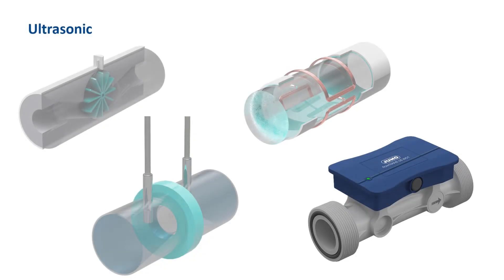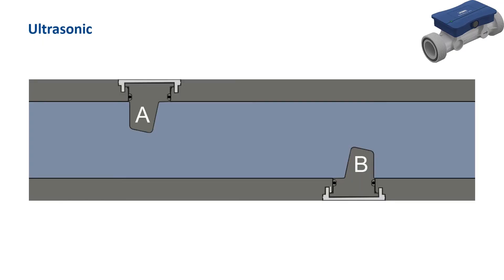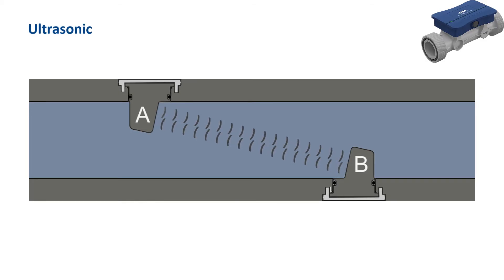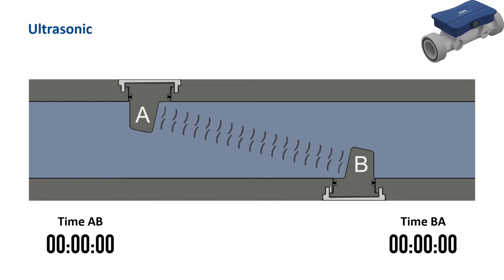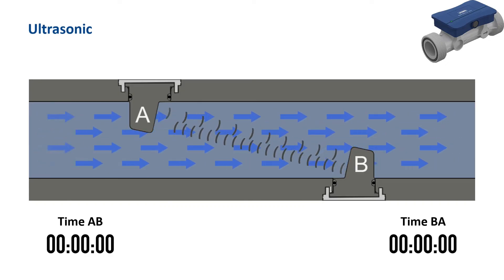Finally, the ultrasonic flow meters of the FlowTrans US series. JUMO ultrasonic flow meters operate according to the Transit Time method. Two transducers are located in the pipe section, shown here as A and B. These work according to the piezoelectrical effect and send and receive ultrasonic waves. If the medium is stationary, the recorded transit time of the ultrasonic waves from A to B and from B to A are the same. If the medium begins to flow, the ultrasonic waves become faster in the direction of flow. The greater the difference between the transit times in both directions, the greater the velocity of the flow medium. The time difference is therefore a measure of the flow velocity.